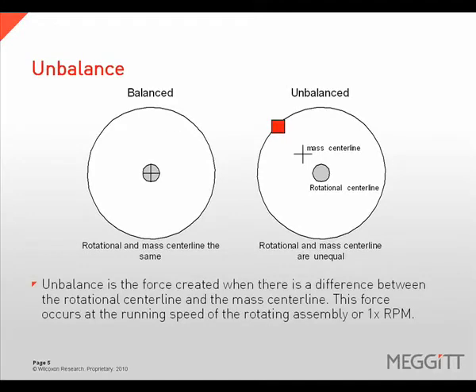Unbalance is the force generated when a difference between a rotational centerline and a mass centerline exists. This force occurs at running speed of the rotating assembly, or 1 times RPM. The vibration amplitude due to imbalance will increase by the square of the speed — if you double the speed of the rotor, vibration amplitude due to unbalance will increase by a factor of 4.